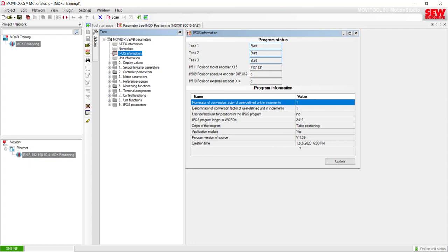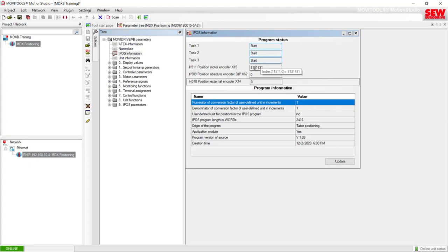The IPOS information gives the date it was loaded to the MOVIDRIVE and tells me all the tasks for the program are currently started. Below the tasks you'll see terminal numbers X15, X62, and X14. X15 is the motor encoder. Terminal X62 is common with the DIP encoder card or encoder options with an SSI encoder type input. X14 is an encoder option for an external encoder input or simulation out for synchronous operation. I'm currently not using anything plugged into any of these terminals, so the value is currently at zero.